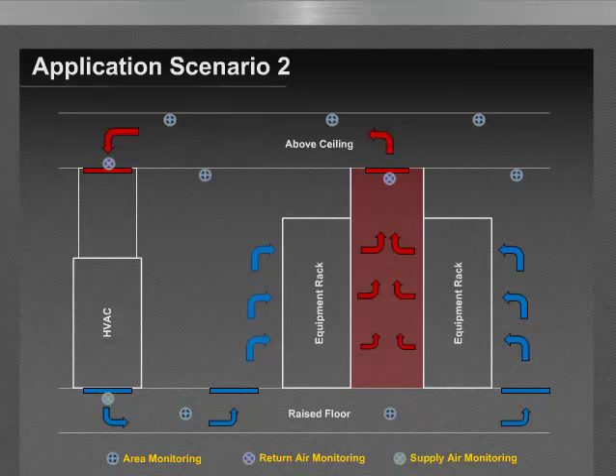So in this configuration here, we're detecting it before it gets to the ceiling. We're also detecting it at the return air path. We're detecting it at the supply side of the HVAC unit. If there's an event in the HVAC unit, we potentially want to detect that before it spreads smoke through the rest of the data floor or data hall.